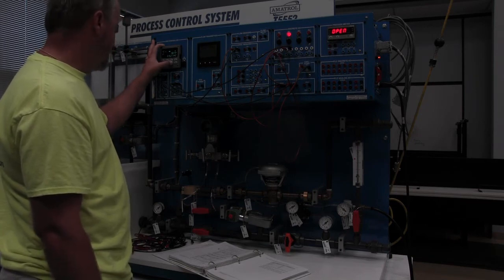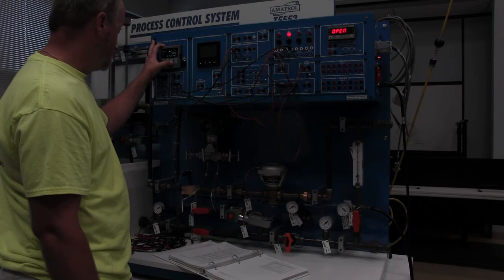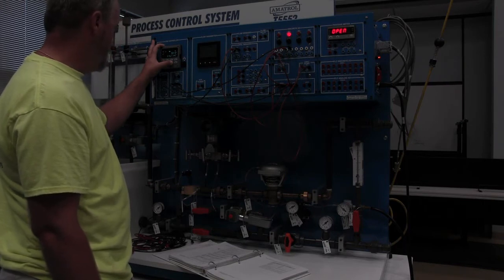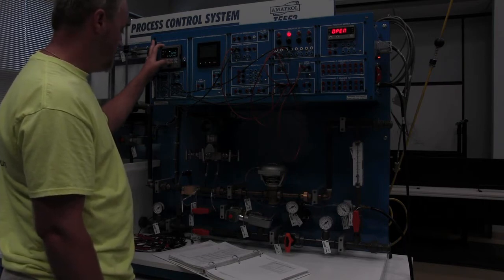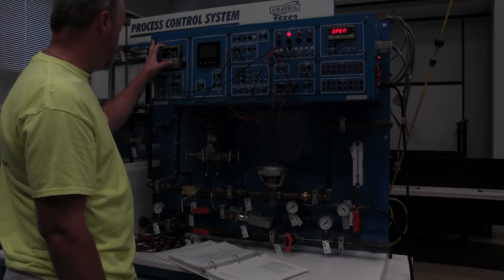So basically what I'm doing now is setting up my low alarm and my high alarm. Anything below 1 is going to be a low alarm. Anything above a 5 is going to be a high alarm.